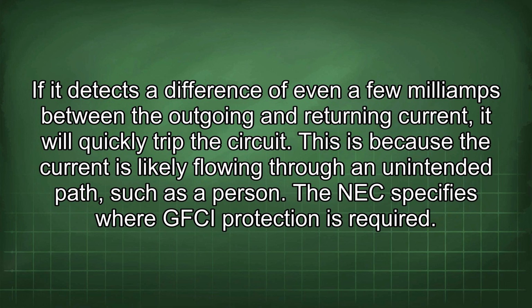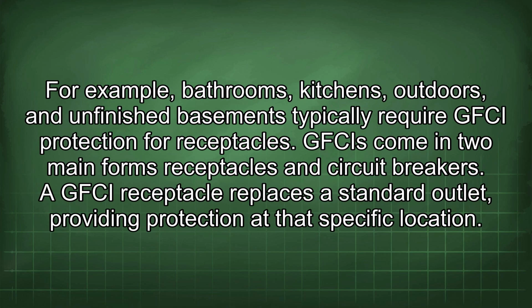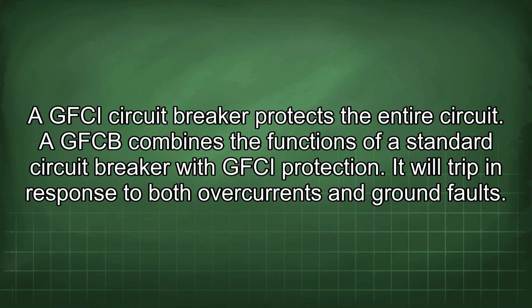The NEC specifies where GFCI protection is required. For example, bathrooms, kitchens, outdoors, and unfinished basements typically require GFCI protection for receptacles. GFCIs come in two main forms: receptacles and circuit breakers. A GFCI receptacle replaces a standard outlet, providing protection at that specific location. A GFCI circuit breaker protects the entire circuit. A GFCB combines the functions of a standard circuit breaker with GFCI protection. It will trip in response to both overcurrents and ground faults.